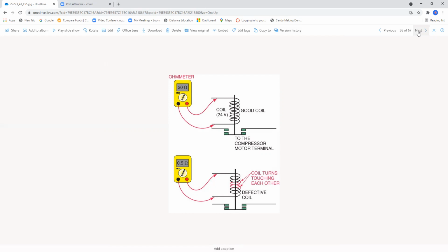Now, if you take a look at the second picture, look what happened. The turns are touching each other. We have a partial short. Look what happens to the ohms value: it drops significantly. Very important when you are checking out the electrical solenoid on the 4-way reversing valve that you get the proper ohm rating. If you do not get the proper ohm reading, that solenoid usually is field replaceable without taking out the whole 4-way valve. That's an easy part to change out.